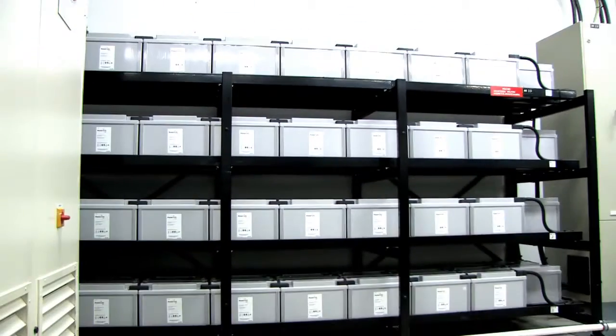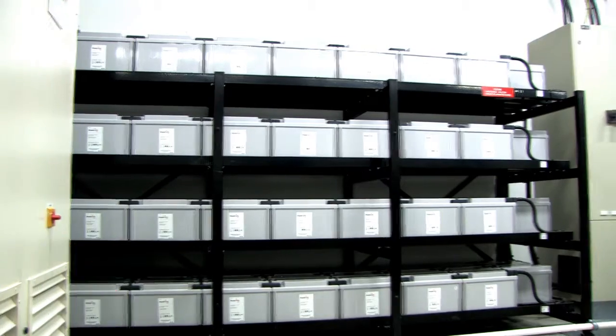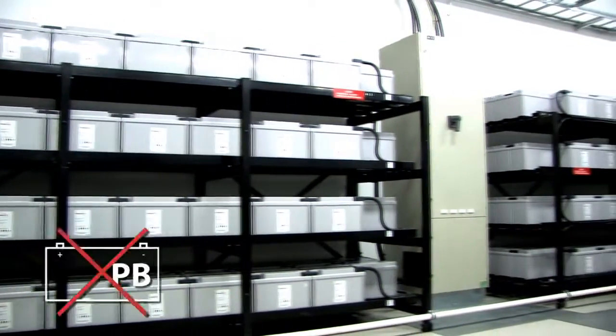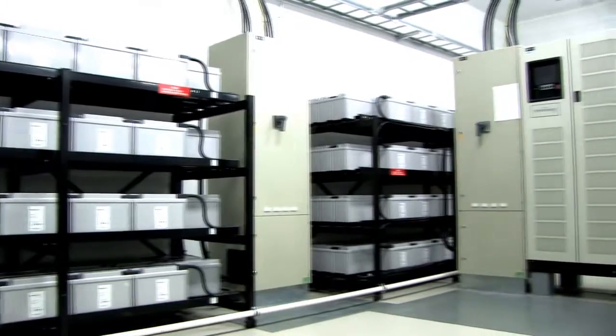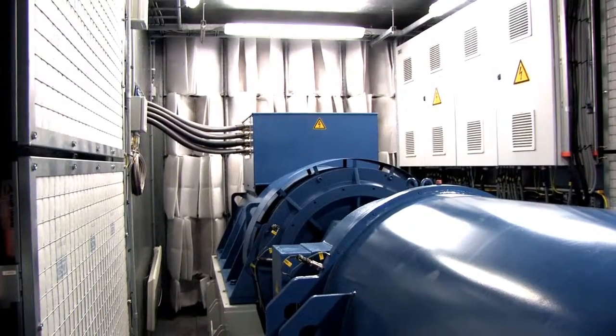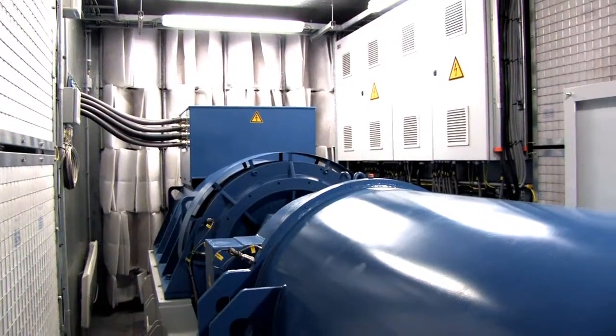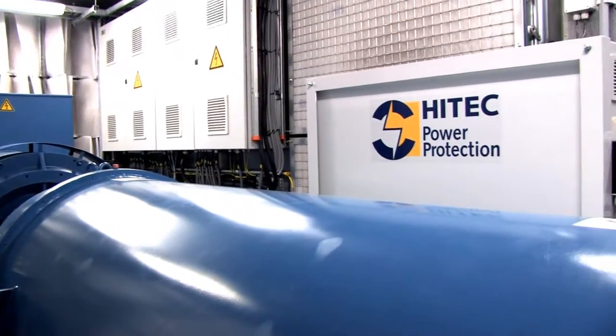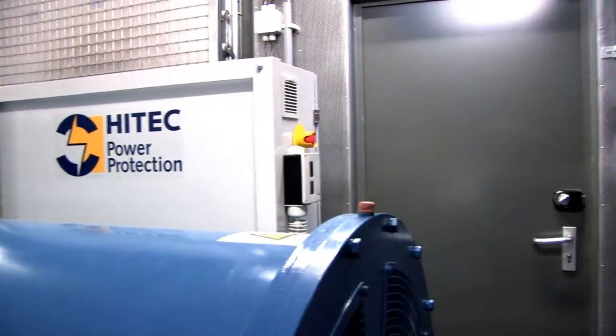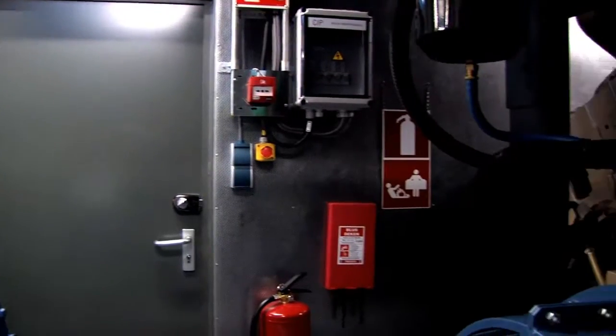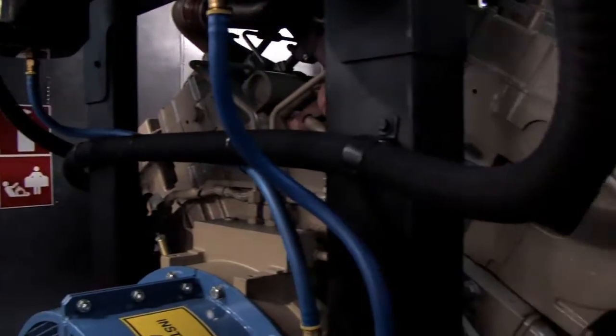In the case of a power outage, most data centers are powered by an arsenal of batteries. In our new model, there are no batteries, which means no disposal of spent acids or lead. We can maintain normal operation by using a flywheel generator, which gives us enough time to start up a diesel generator that will run until the power outage is fixed. This is a more sustainable way to use energy and reduces the amount of waste.